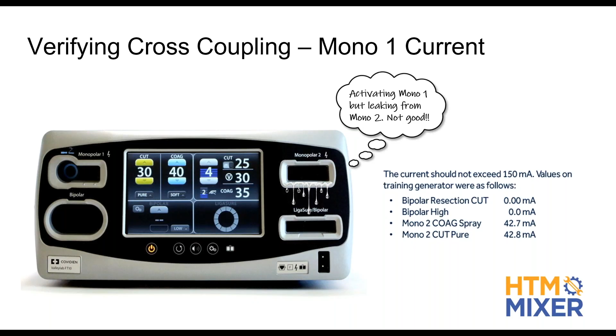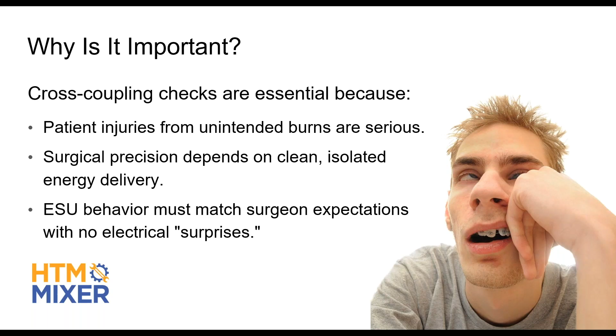That's leakage. And so really, when we're doing cross couplings, if we're activating mono 1, we want to take a look at mono 2. Now, there is some leakage out of mono 2 because it's using the same circuitry. So you are going to get some leakage if it's using the same circuitry, but you should have nothing between the mono 1 and below the bipolar or the LigaSure, completely separate circuits. So you want to make sure that you're doing those checks. And the reason: patient injuries, surgical precision, and the ESU behavior must match the surgeon's expectations. So that's why we do those. It's a big part of the PM for us in class.